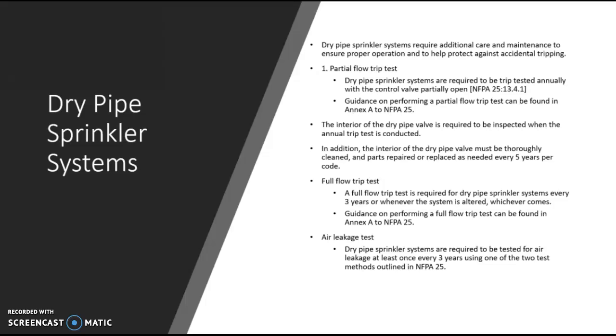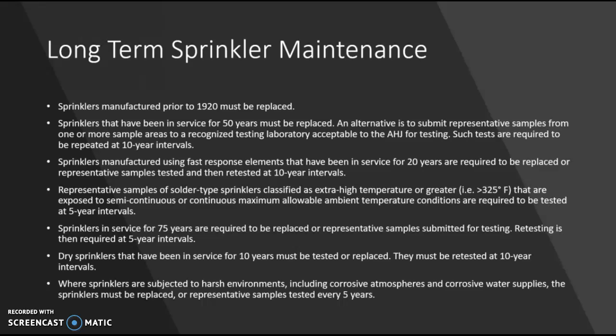And then once again, the last thing is the air leakage test, and it's required to be tested at least every 3 years. There's one of two methods that you can use that is outlined in NFPA 25 in the annex, naturally. Long-term sprinkler maintenance. Now, this is something that we find in a lot of older buildings, and sprinklers that were manufactured prior to 1920 have to be replaced. Sprinklers that have been in service for 50 years must be replaced.